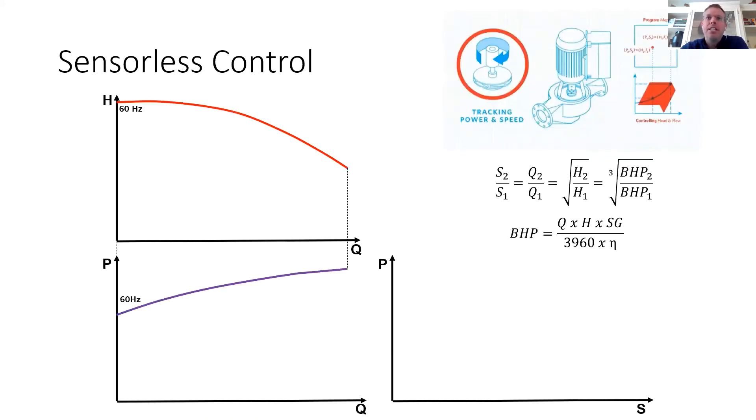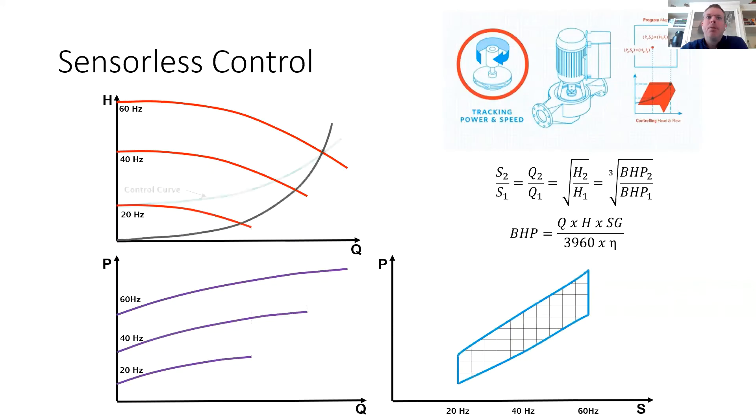So visually, you can see how power and speed are related back to flow and head. Check out this example map. Additionally, we program into the controller a quadratic control curve that takes into account the minimum head required to satisfy your most remote load and draws a quadratic control curve up to design flow and head.